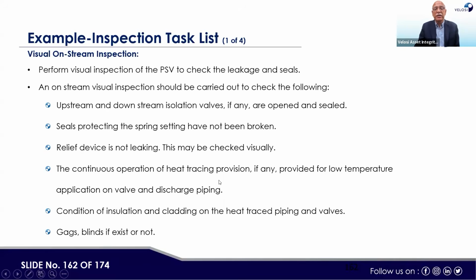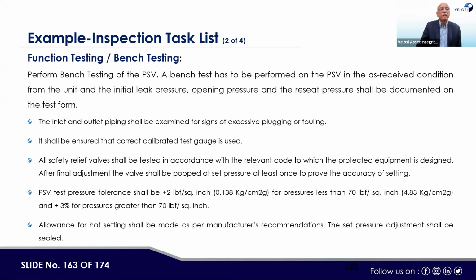The continuous operation of the heat tracing provision, if any, provided for the low temperature application of the valve and discharge piping. Condition of insulation and cladding on the heat traced piping and valve. Then gags and blinds, whether they exist or not. Then here, functional testing, bench testing, what we normally do: the inlet and outlet shall be examined. It shall be ensured that the correct calibrated test gauge is used. All safety valves shall be tested in accordance with the relevant code to which the protected equipment is designed. After final adjustment, the valve shall be popped at set pressure at least once to prove the accurate setting. PSV test pressure range would be followed. Allowance for the hot setting shall be made as per the manufacturer recommendations.